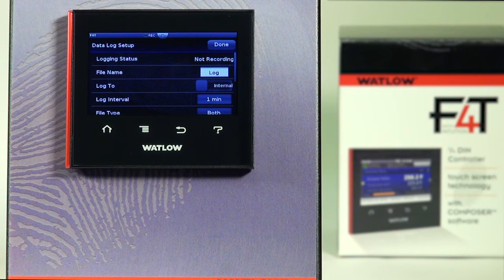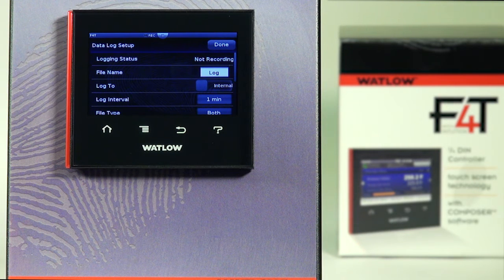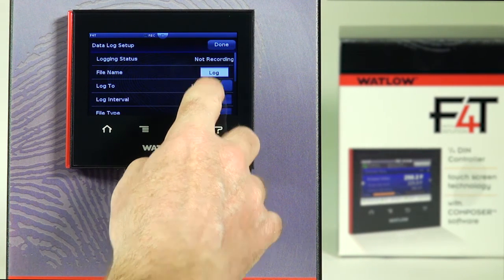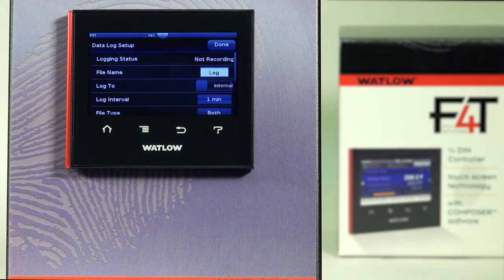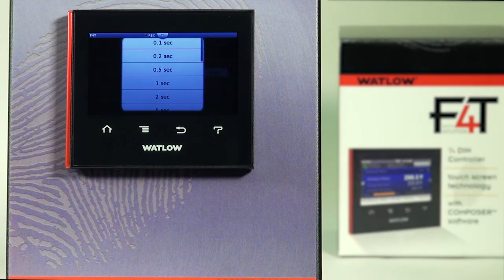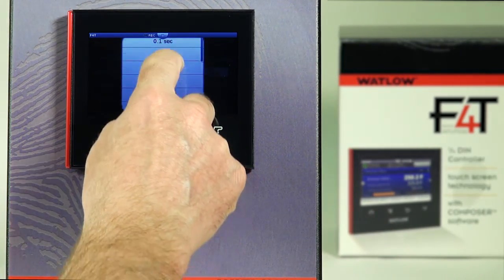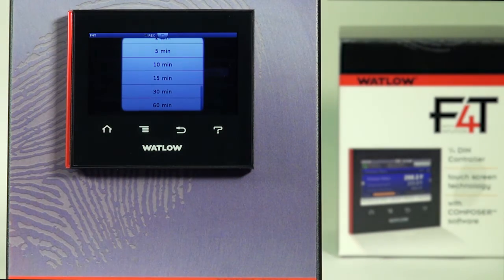'Log To' — you can log to internal memory; we have 80 megabytes of internal memory available, or you could log directly to a USB memory device plugged into a host port. 'Log Interval' is where you can set the frequency for data logging. You can record as fast as 0.1 second with fixed increments all the way up to 60 minutes.